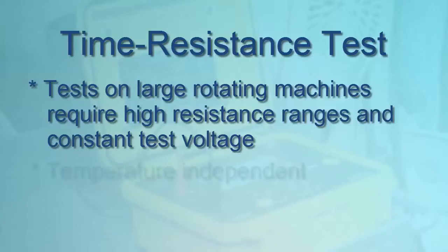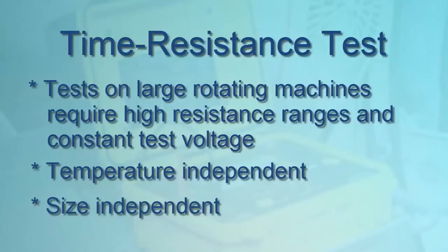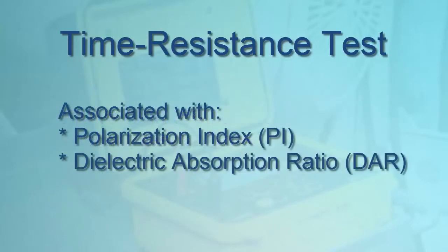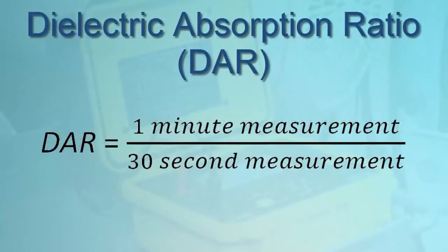The time resistance test is also independent of the size of the system under test. It is sometimes associated with two values: the polarization index (PI) and the dielectric absorption ratio (DAR). The polarization index is derived by dividing the 10-minute resistance measurement by the 1-minute measurement. The dielectric absorption ratio is calculated by dividing the 1-minute measurement by the 30-second measurement. Although DAR is no longer commonly used with new insulation systems, it may still have applicability when testing older insulating materials.